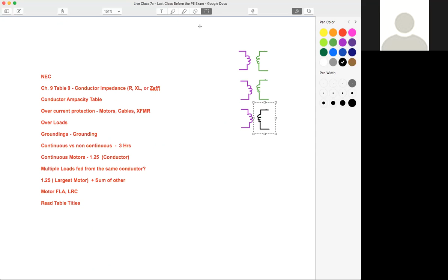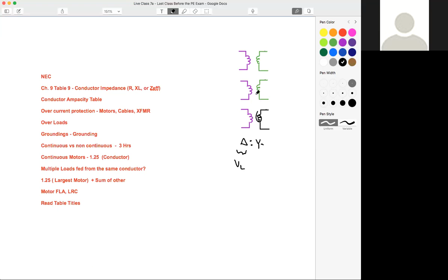This voltage right here, is that equal to our line voltage or our phase voltage? It's the phase voltage of the delta, but it's also equal to our line voltage of our transmission line, right? And if we look at a Y, each one of those windings is going to be on a phase. Just like on our Y, each of these windings exists on the phases. I hope this isn't too small.